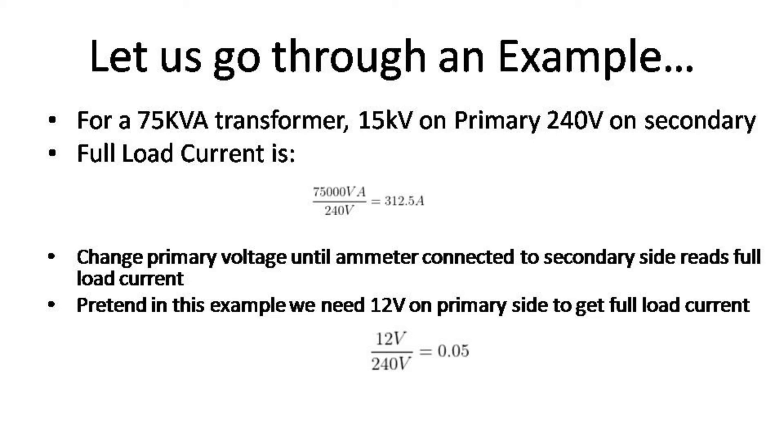In this particular example, let us just pretend that we get our full load current when we inject 12 volts into the primary side of the transformer. Then the impedance ratio is equal to 12 divided by 240 volts, which equals 0.05.